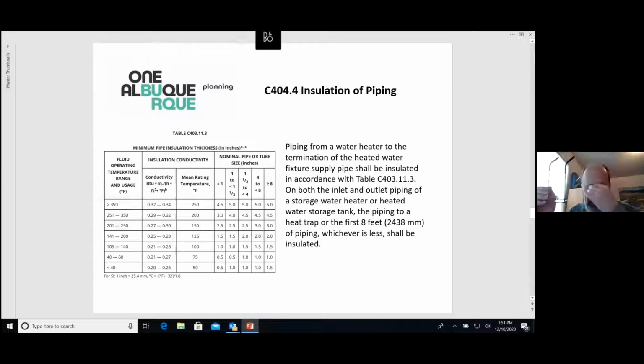So in an existing building, let me see if I got the question right. In an existing building, you're replacing a water heater that has a heat loop. I apologize, could you read that again? Yes, sir. How is the heat trap insulation dealt with in existing buildings that do have piped heat traps, and the replacement water heater does not have the heat trap integral to the unit, an uninsulated heat loop?